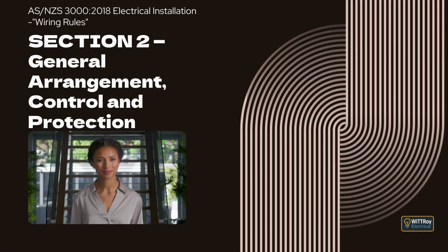Clause 2.3.4 Additional isolating switches. Clause 2.3.4.1 Electrical installation in an outbuilding. This clause explains when an outbuilding needs to be treated as its own electrical installation. If the outbuilding has a maximum demand of 100 amps or more per phase, and it has its own switchboard, then it must be treated as a separate installation. This means it will need its own isolating switches and its own main switch arrangements.